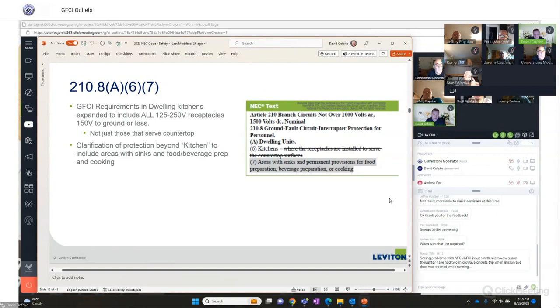Let's put it that way, because the one thing that I'll bring up is nobody at this time makes a 240 volt receptacle that's GFCI protected. The only way you're able to protect that circuit is through a circuit breaker, a 2-pole GFCI circuit breaker. So basically what this article is talking about is these 240 volt circuits, your stove, your electric range in your kitchen, now need to be AFCI and GFCI protected. Wow.